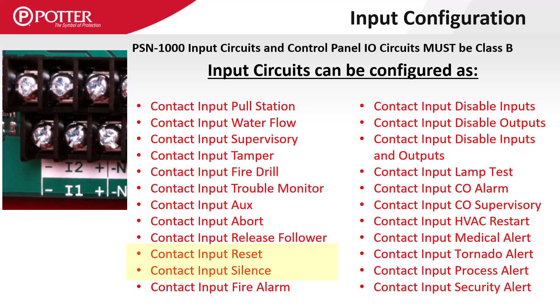Abort and Release Follower are point types used in releasing applications. Contact Input Reset and Silence offer the ability to remotely reset or silence the control panel. Contact Input Fire Alarm is used with alarm-causing devices other than pull stations and water flows. There are options to use a remote switch to disable groups of input or output devices and circuits. Contact Input Lamp Test is used to test LED outputs. CO Alarm and CO Supervisory are point types used with conventional CO detectors.